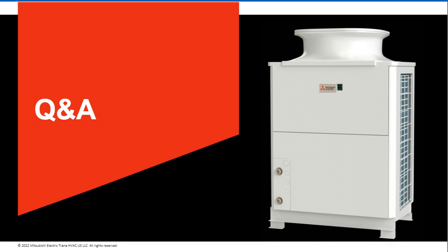Okay. Jeff, do you want to add anything, or can I move to the next? Yeah, I think it's really dependent on building size. If it's a large hotel, you don't want it to take 20, 30 minutes for the shower to get warm if you didn't have the recirc loop. And so that's where it's really critical to have the swing tank, so that there's that maintenance loop and you're not having a huge delay in getting your domestic hot water.